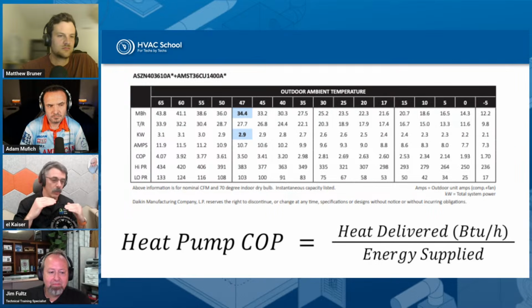And anytime we see higher than a 1 on the COP scale, that means that for the same amount of energy as electric heat delivers in BTUs, the heat pump is delivering like 1.5 or 1.8 times that, or 2 times that, or 4 or 5 times that much heat for the same wattage input. So it's using less energy for the same amount of heat being transferred into the house, because we can transfer it from outside to inside with refrigeration more efficiently.